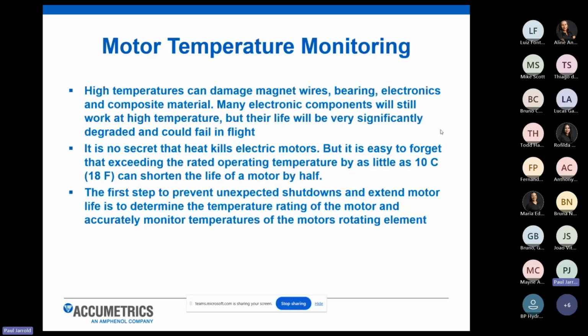So the first step in preventing unnecessary shutdowns and extending the life of your motor is determining the real-time temperature data of that motor during operation. Customers of ours that have used this system oftentimes are driving their motors well beyond what they were designed to do, in a rolling mill application for steel or aluminum or pulp and paper, any large drive rolling type motors. The customers are driving those machines very hard. They're trying to get a lot of throughput through their plant and run these 24/7, 365 days a year, continuous, and they generate a great deal of heat inside of the motor armature windings.